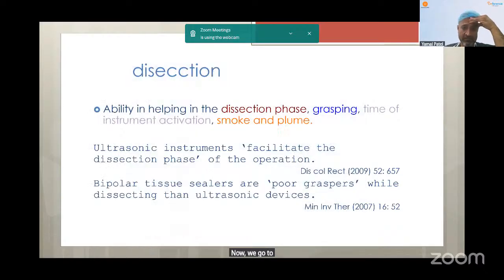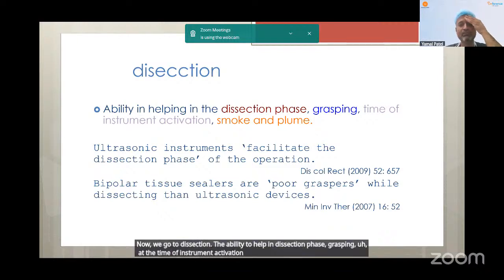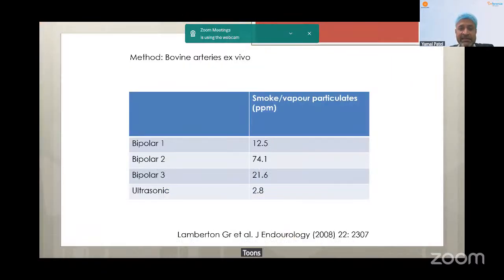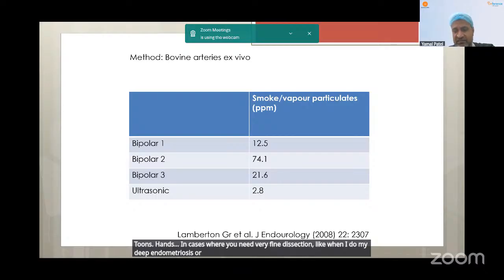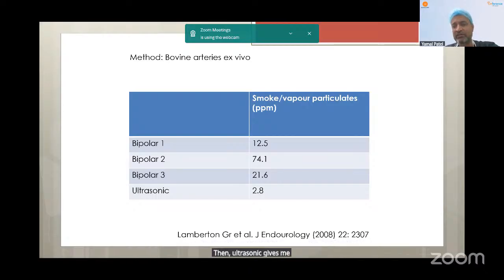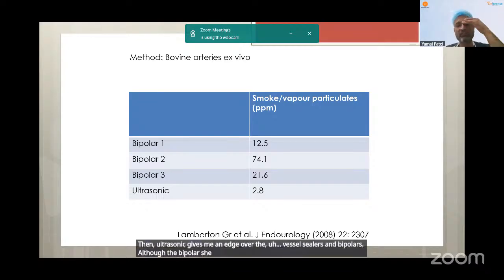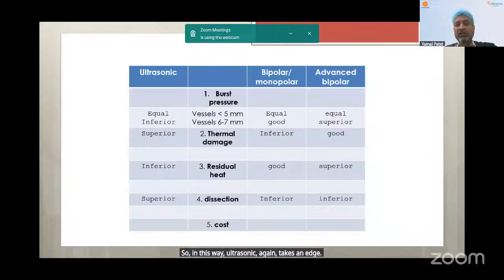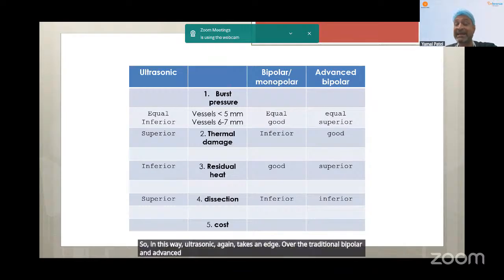Now we go to dissection: the ability to help in the dissection phase, grasping at the time of instrument activation, and the smoke and plume. Ultrasonic really facilitates dissection by the cavitation effect, whereas the bipolar sealers are poor graspers and also not very good dissecting tools. Hence, in cases where you need very fine dissection, like when I do my deep endometriosis or bowel endometriosis, ultrasonic gives me an edge over the vessel sealers and bipolars, although the bipolar shears can also be used for similar procedures. So ultrasonic again takes an edge over the traditional bipolar and advanced bipolar in dissection.